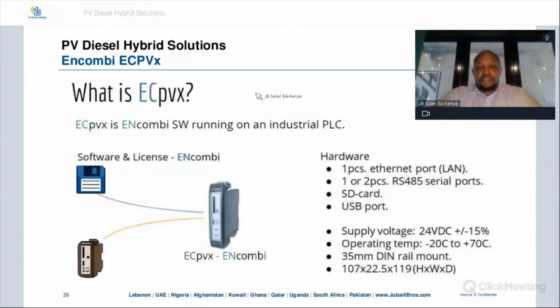So the ECPVX, the specific fuel save controller, has a software that runs on an industrial PLC. PLC is a programmable logic controller. And in this ECPVX, you have the software and license that is built in, and you have the hardware component. And the hardware components, you have the Ethernet port, 1 or 2 RS-485 serial ports. You have an SD card where you can save your data, and a USB port. The power supply is 24 volts DC, plus or minus 15%. It has an operating temperature range of negative 20 degrees Celsius to 70 degrees Celsius. And these are the rail mounts requirements, as well as the dimensions of the ECPVX.